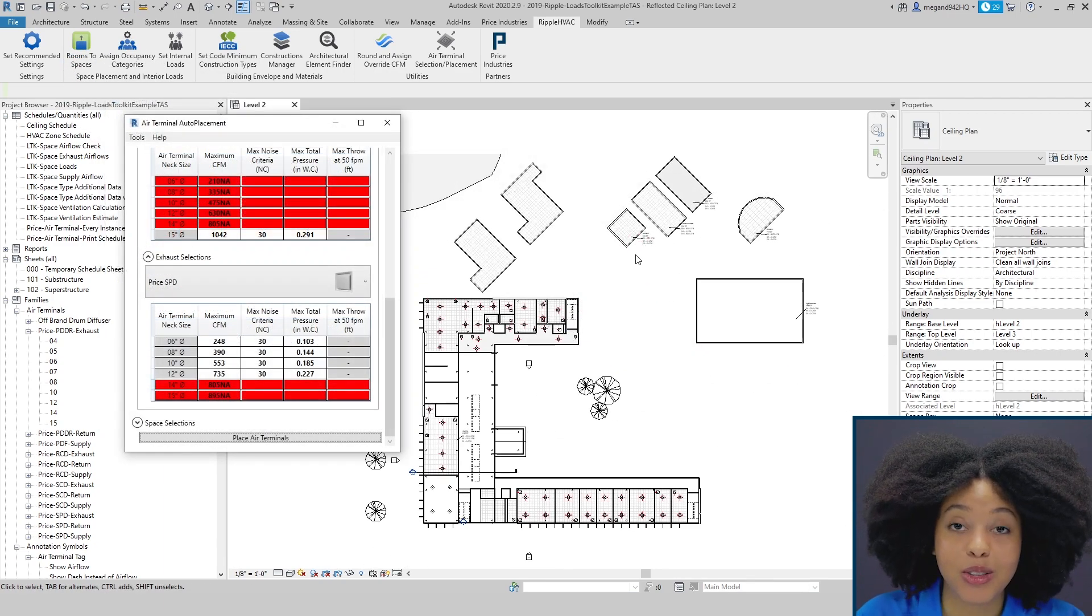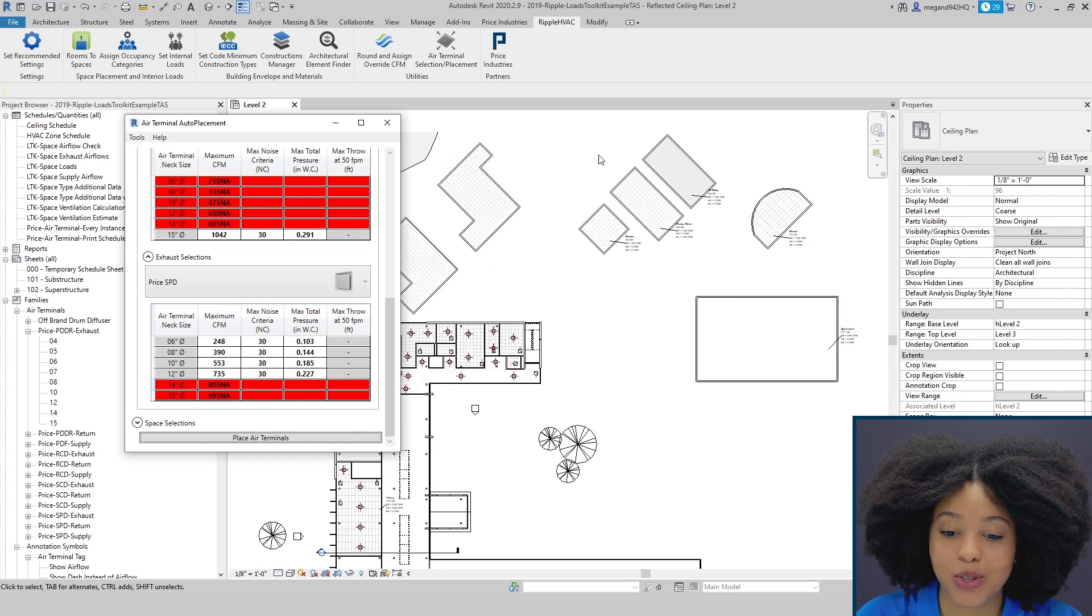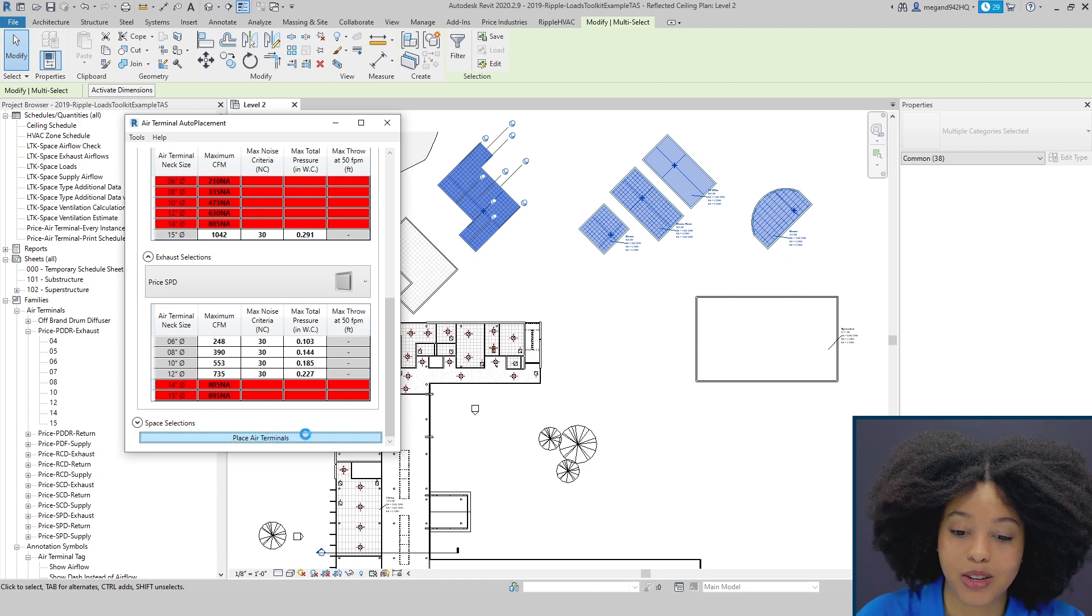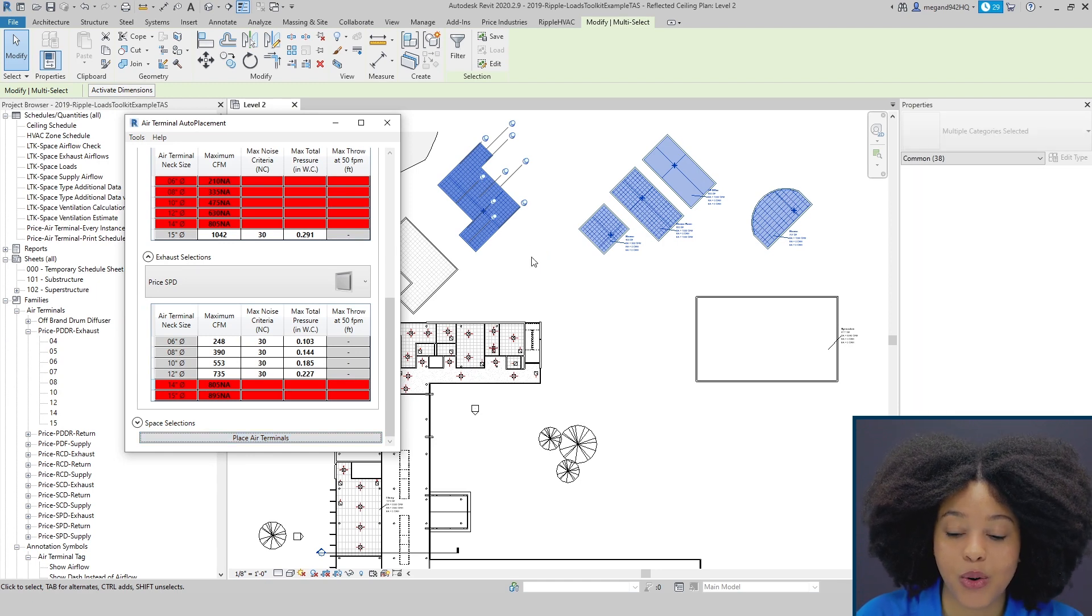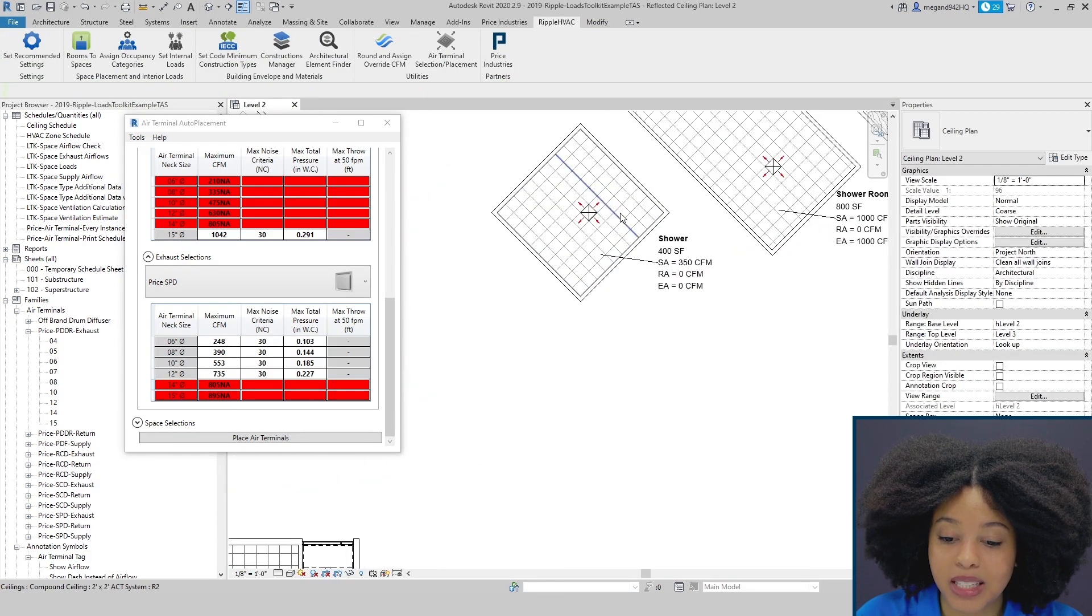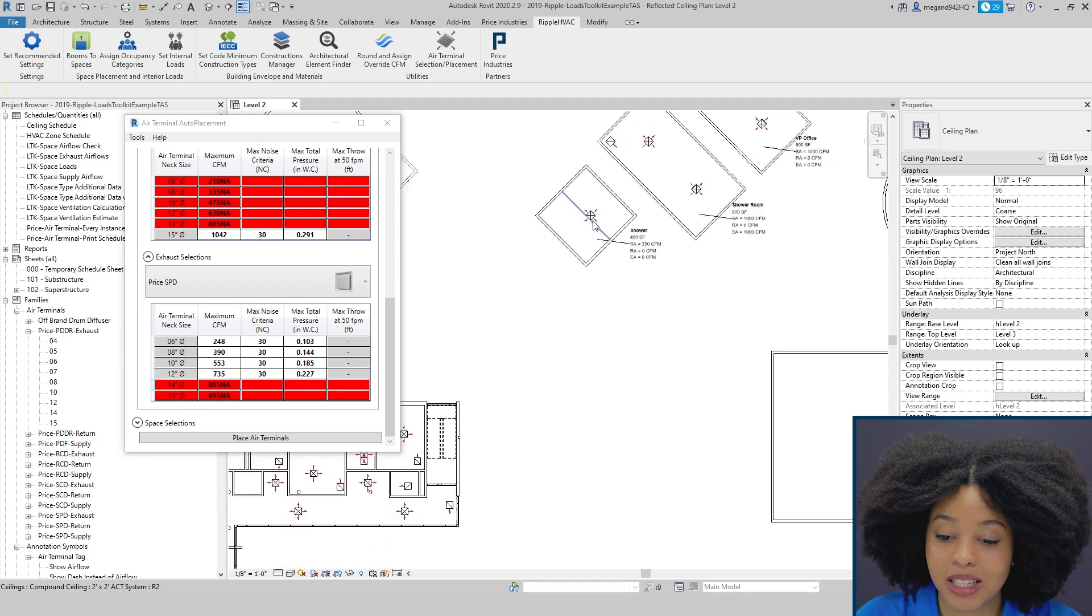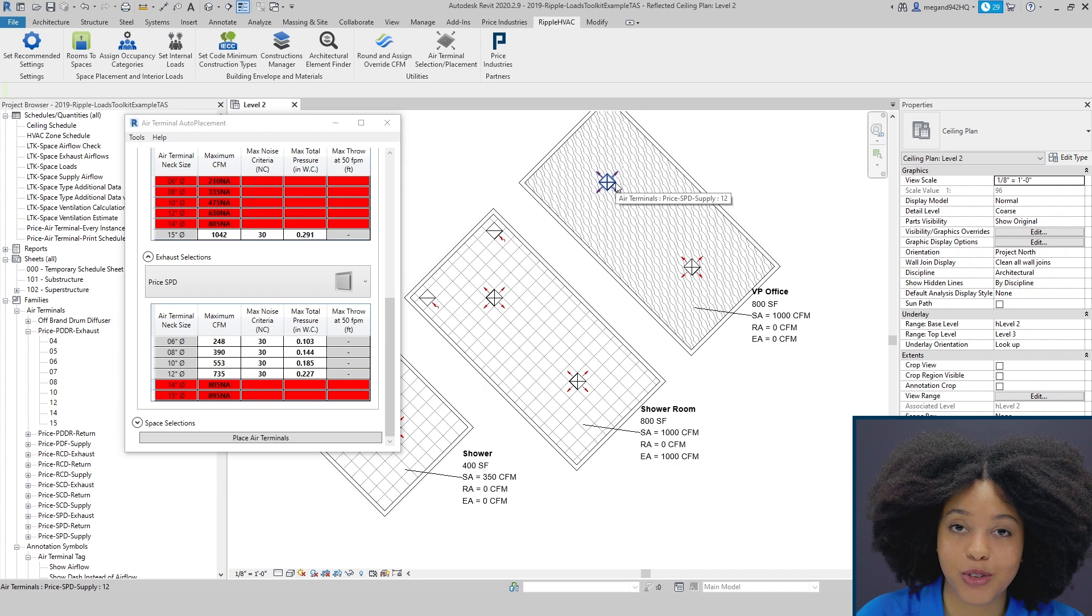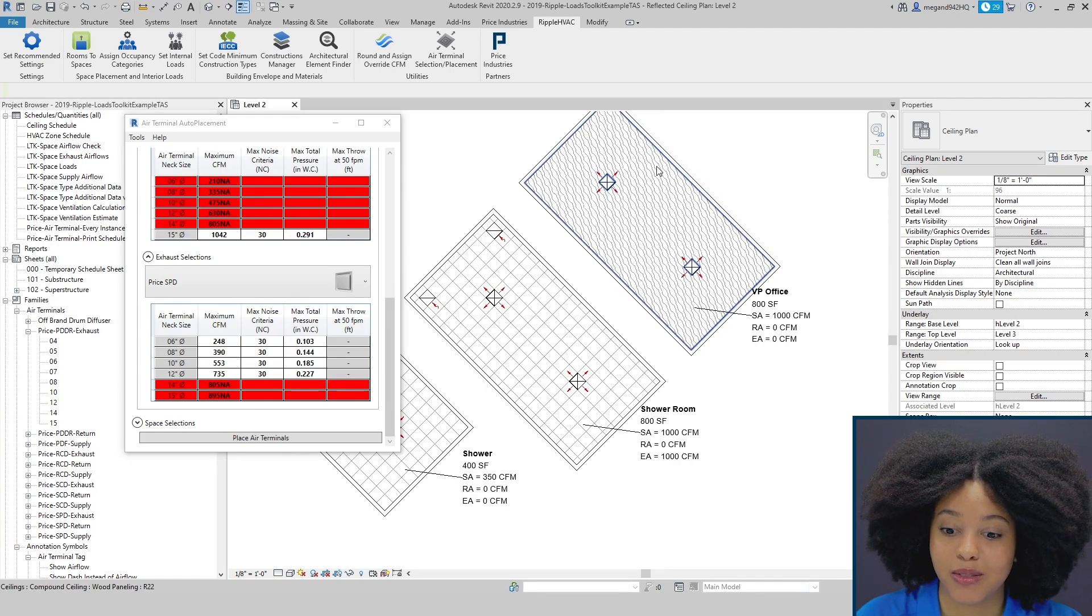The tool isn't limited to placing diffusers just at a right angle. It can also do spaces at an angle as well as curves. By simply selecting the spaces here and pressing place air terminals, we can see that it will always align the geometry of the diffuser along the grid or the geometry of the wall. Here we can see that it didn't just place the diffuser directly in the center, it ensured proper alignment with the wall and the ceiling grid. In this example where there is no ceiling grid, it just aligned the diffusers to be parallel to the lines of the wall.